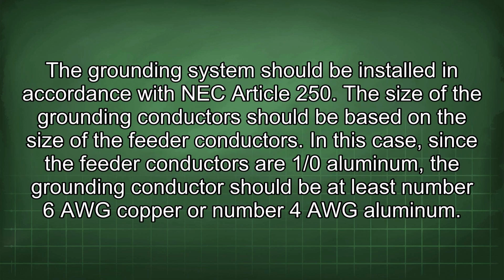The grounding system should be installed in accordance with NEC Article 250. The size of the grounding conductor should be based on the size of the feeder conductors. In this case, since the feeder conductors are 1/0 aluminum, the grounding conductor should be at least number 6 AWG copper or number 4 AWG aluminum.